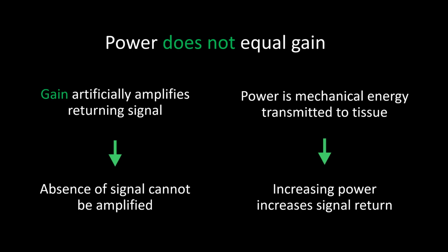The amount of ultrasound energy imparted to the medium is dependent on the pressure amplitude variations generated by the degree of transducer expansion and contraction. This is controlled by the transmit gain applied to a transducer. Power is the amount of energy per unit time introduced to the medium. Intensity is the concentration of the power per unit area in the ultrasound beam. Power does not equal gain.